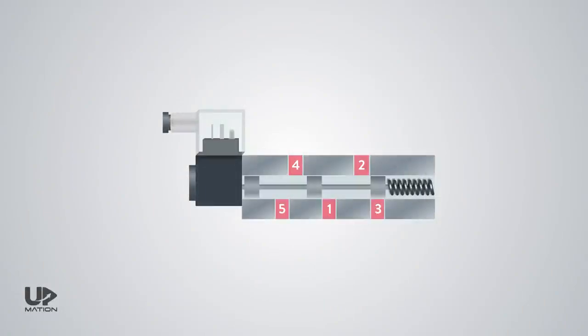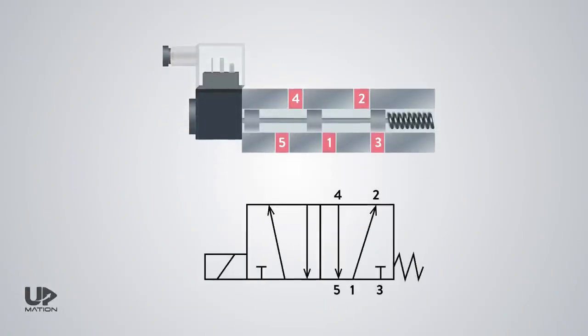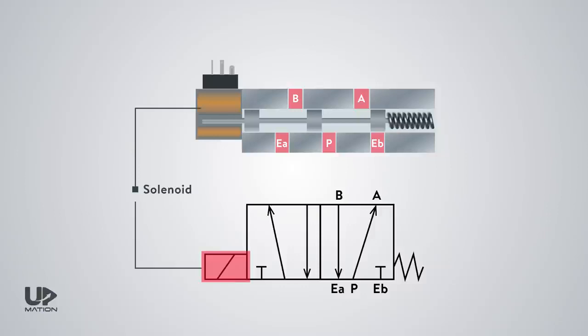As I've mentioned, this valve has 5 ports and this is the ISO designation of the ports, which is a common practice. But sometimes, you may see an alternative designation of the ports in DCVs by alphabets, in which the P is for power or pressure that comes from the air source. The EA and EB are for the exhaust ports and the A and B are the output ports to or from the actuator. This is the sign for the electric solenoid and this one is for the spring return.